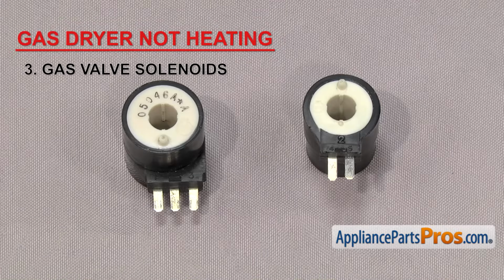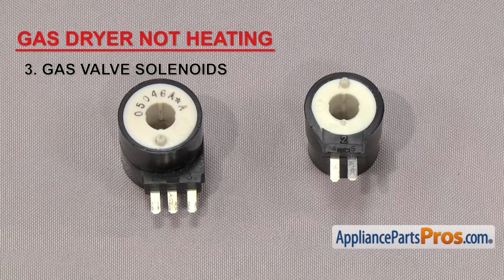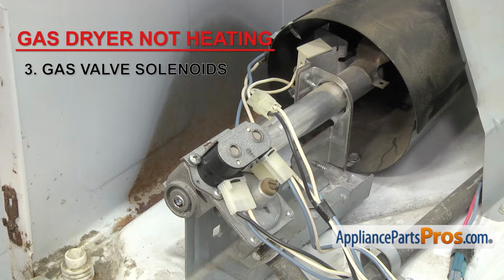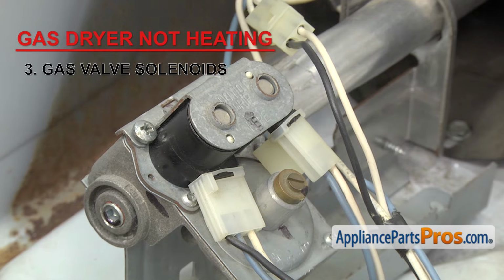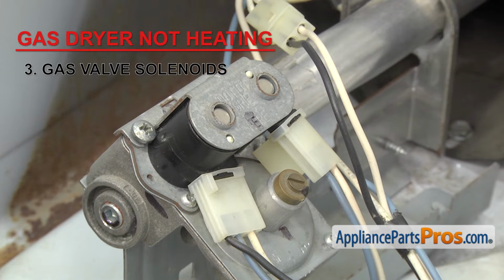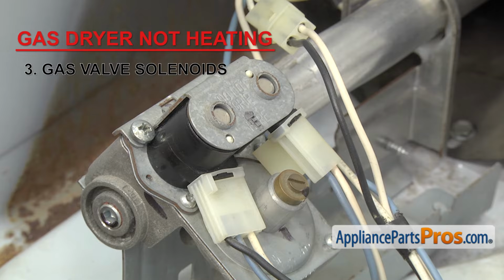Number 3 on the list are the gas valve solenoids. They're what open up the gas valve and allow the gas to flow. The solenoids are part of the burner assembly. They're located on top of the gas valve. One of the symptoms of the solenoids going bad is that they'll quit working after 1 or 2 heat cycles, increasing the drying time until they fail.